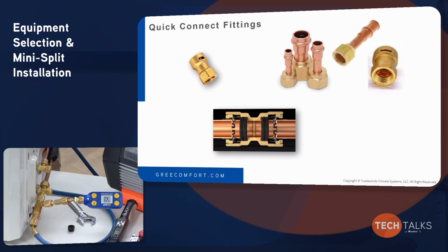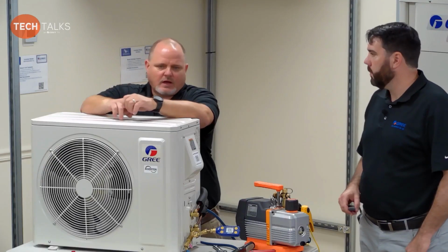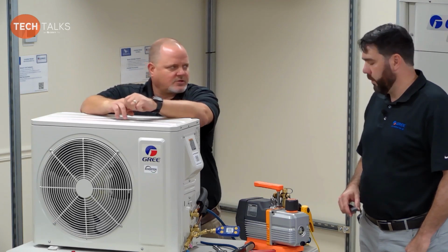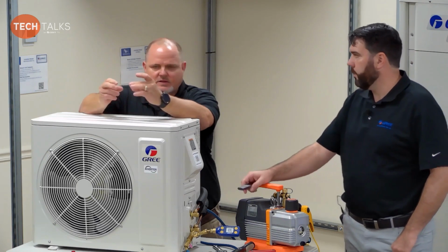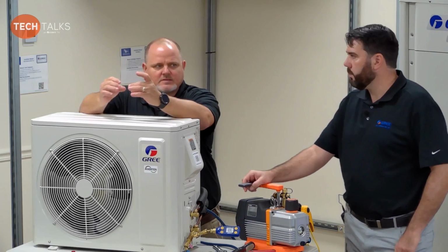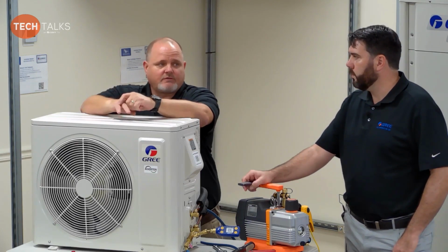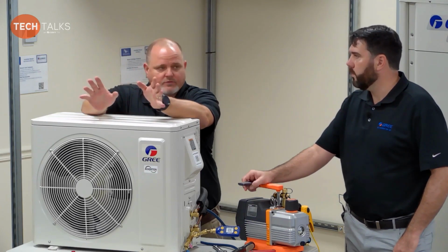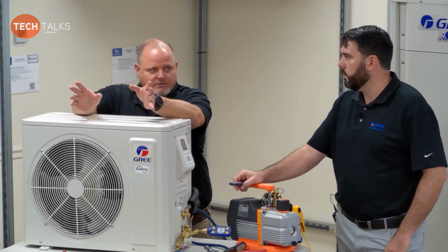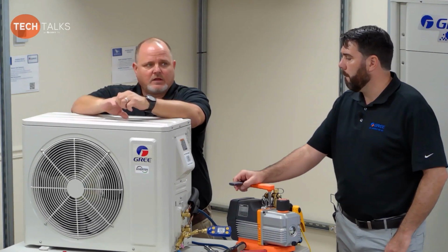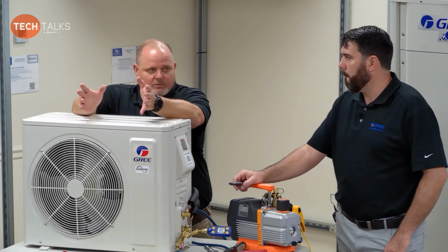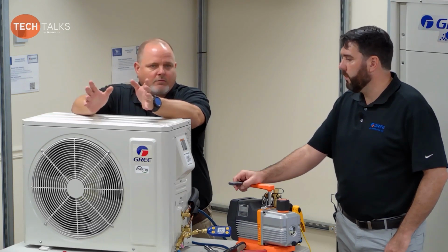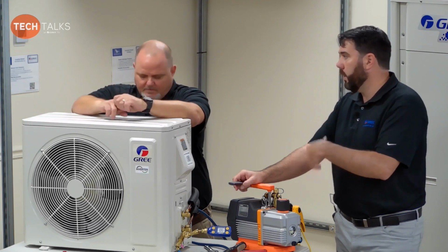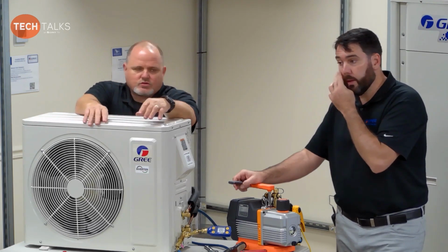When you pull a vacuum, that copper does have an expansion and contraction rate just like anything else, and I think it's just enough, with that void inside the pipe, to cause that fitting to leak. Now, I don't know that for sure. I can't say they're defective fittings. It may have been that the installer didn't put the fitting in right, or it could have been a burr that cut the O-ring. Any little thing like that could affect it.